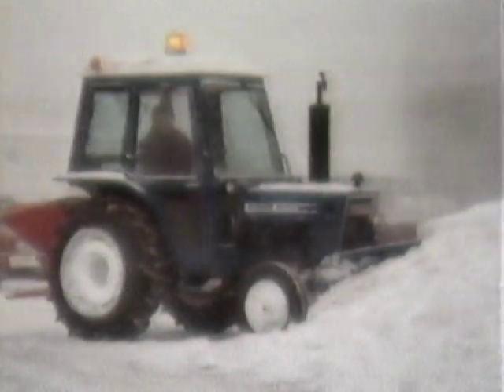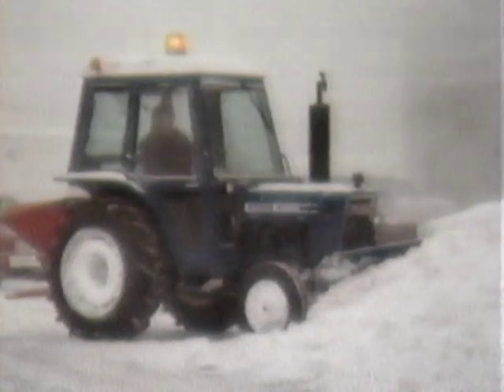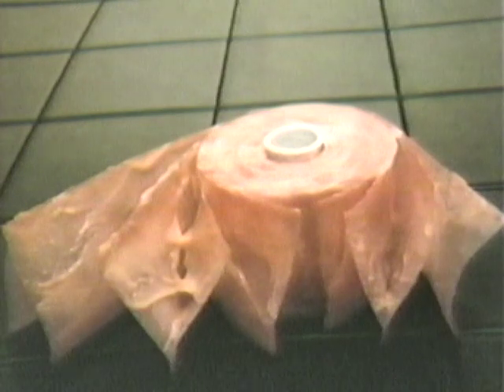Winter brings another serious concern to a diesel fuel system. It's caused by wax. The wax separates or precipitates out of diesel fuel when the ambient temperature drops below the fuel's cloud point. The wax collects anywhere there's a restriction in the fuel line, particularly fine gauzes and filter elements. Fuel lines block up and starve the injection equipment. The engine stops or refuses to start.